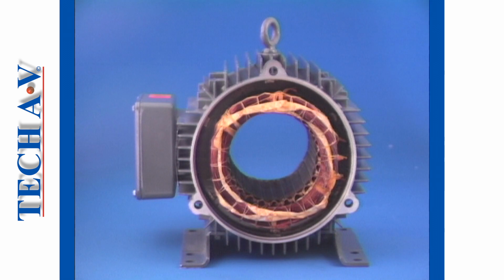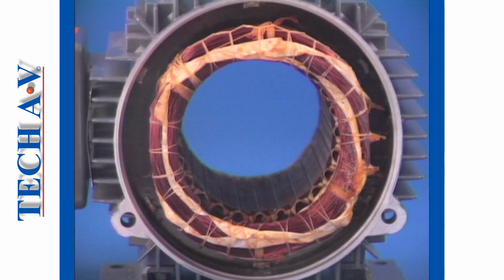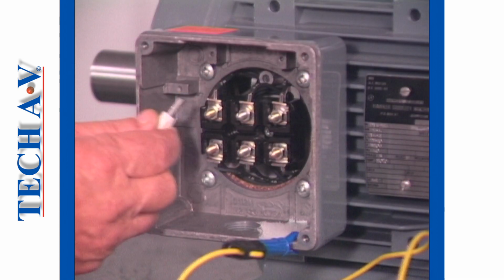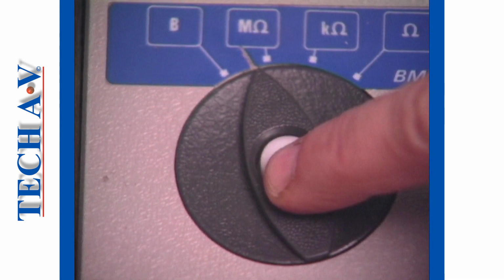In certain equipment, for example an induction motor, many hundreds of turns of wire are looped to form a coil. Each coil loop is insulated to prevent short circuits occurring. Only with a megohmmeter is it possible to assess whether the coil insulation is in good order by measuring the resistance between windings and to earth.